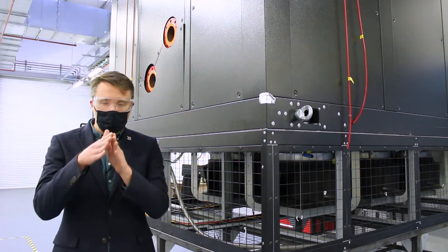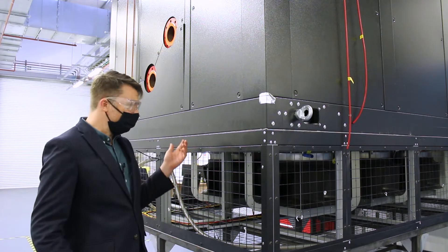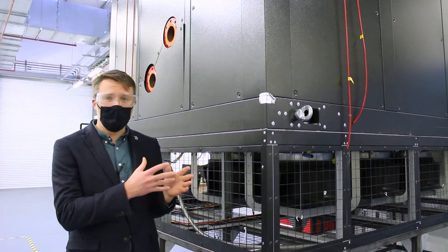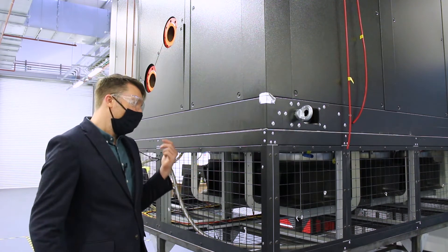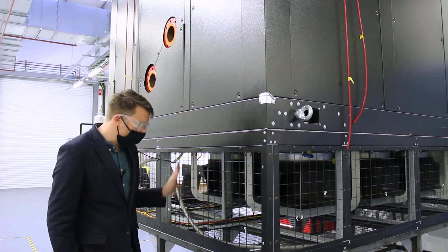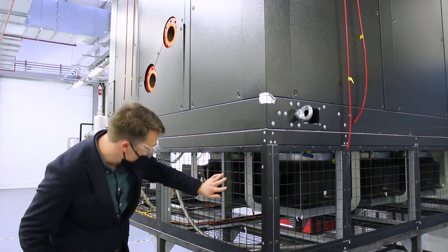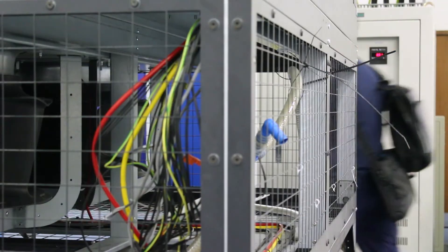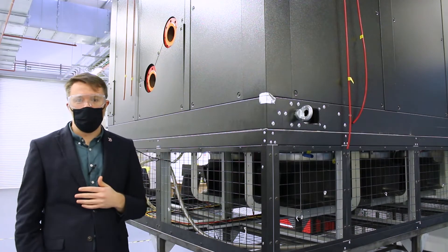In order to achieve that capacity we've added a V-frame design, particularly at higher capacities. Other CRAC units may claim they can do one megawatt because they have the potential capacity through the coil, but they don't always have the airflow to match that capacity. So we've added the most powerful EC backward-curved fans on the market, delivered in the underfloor deck, giving you that powerful cooling that matches the coil potential to deliver one megawatt. We've also done extensive CFD simulation on the product, which has helped us really optimize the airflow completely through the unit.